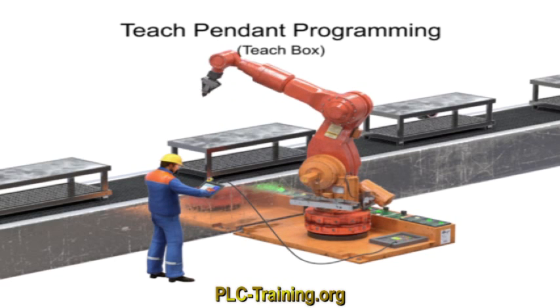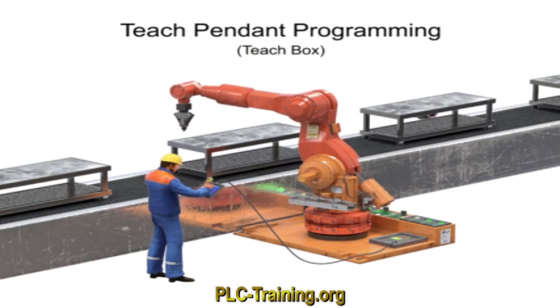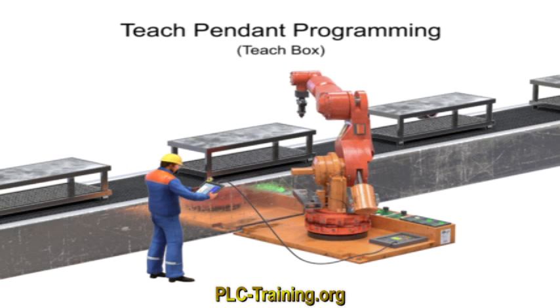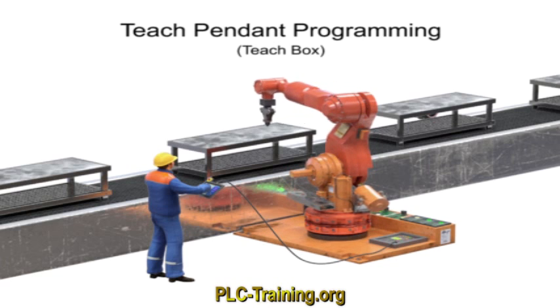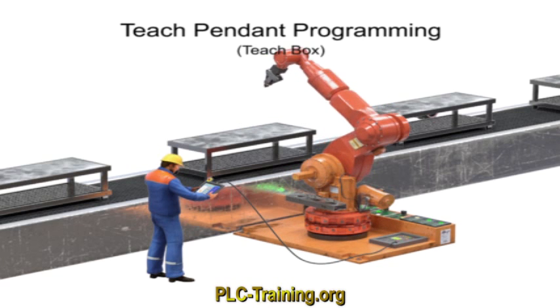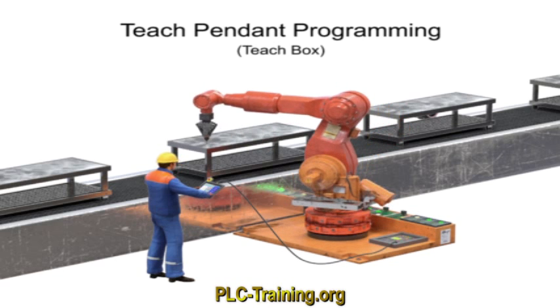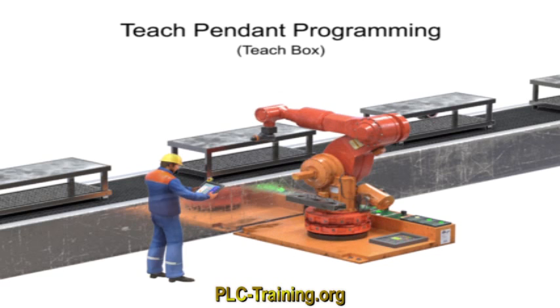The technician has the ability to send the robot to a desired position, inch, or jog to adjust it, and then record the point. The technician may also change the speed, since a low speed is usually required for careful positioning or while test running through a new or modified routine. ANSI standards recommend a speed of no more than 10 inches per second when programming. Once the technician has recorded and tested the program, the teach pendant is disconnected and the robot can operate the stored program at full speed.